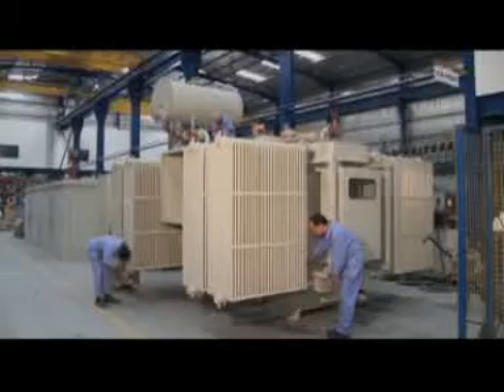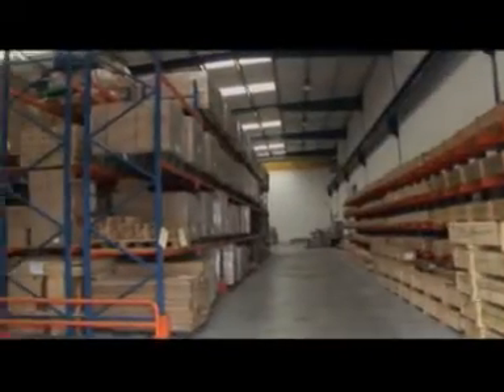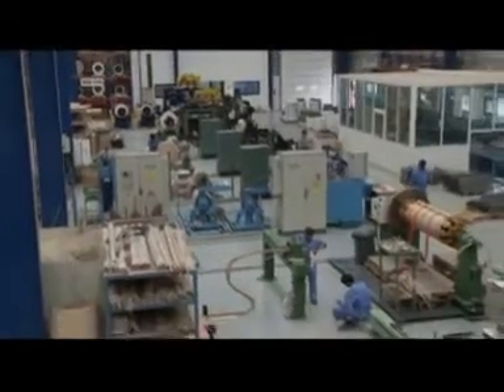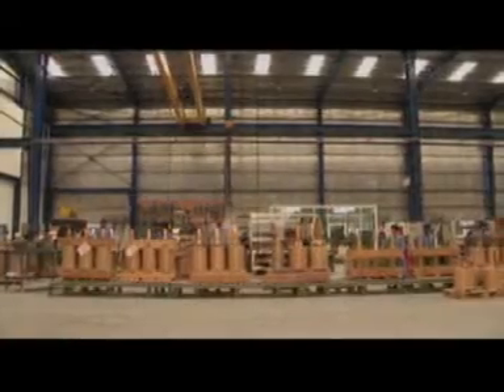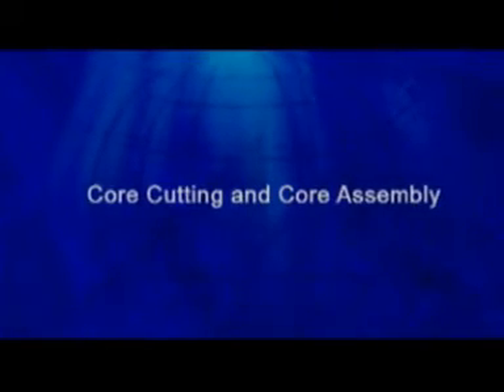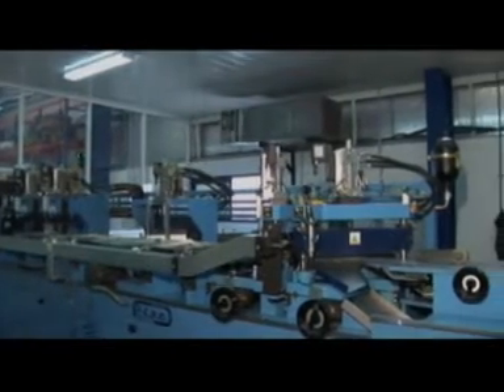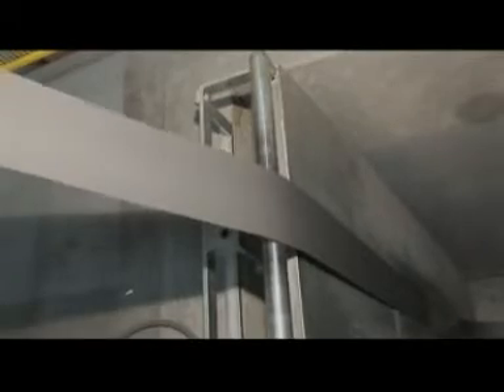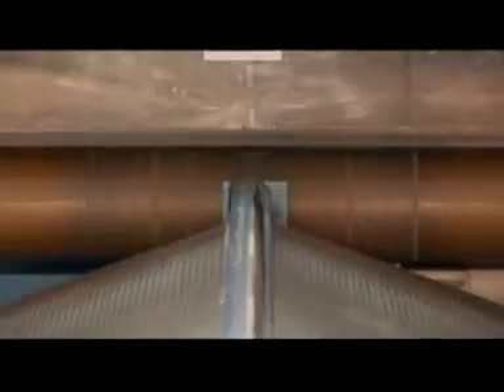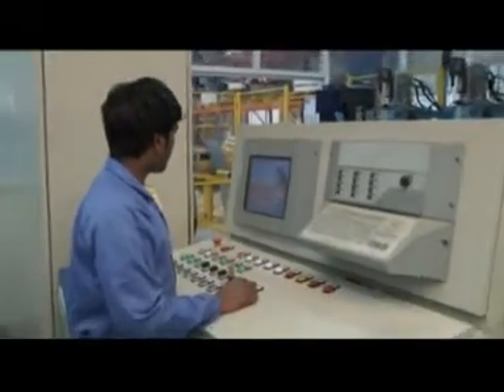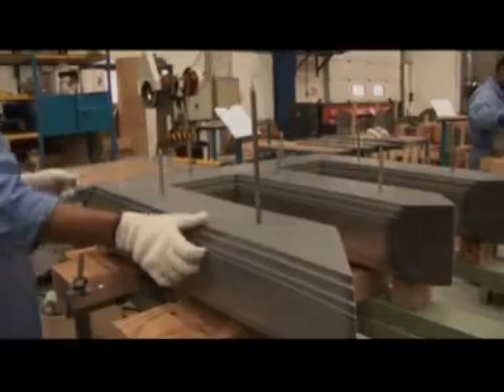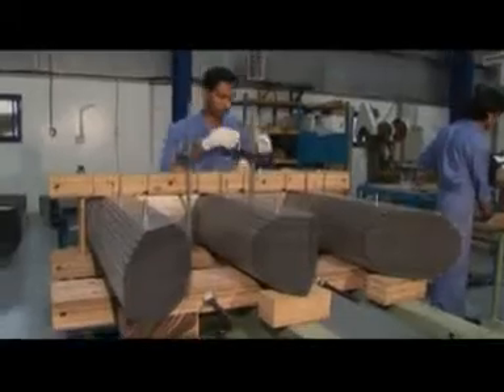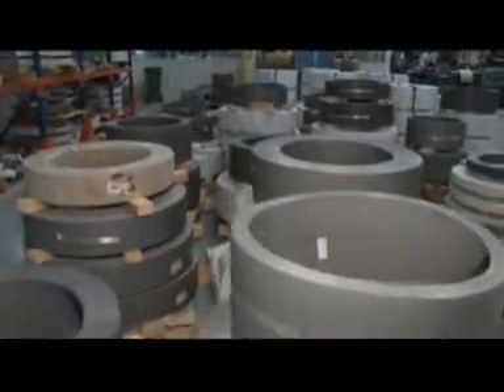At the company's plant, the transformers are manufactured in a well-coordinated and streamlined process. The entire process of manufacturing transformers is carried out in a dust-free, climate-controlled, and fully air-conditioned plant. For all the transformers, high-quality, mostly high B-grade or laser-scribed cold-rolled, grain-oriented silicon steel material is used. A highly sophisticated CNC core-cutting machine cuts core laminates in step-lap core design. The step-lap design ensures very low loss and minimum noise, making GTS transformers more environmentally friendly. Slit cores, sourced from quality suppliers, are cut as per design specifications.